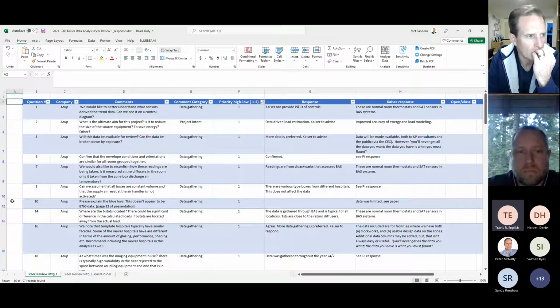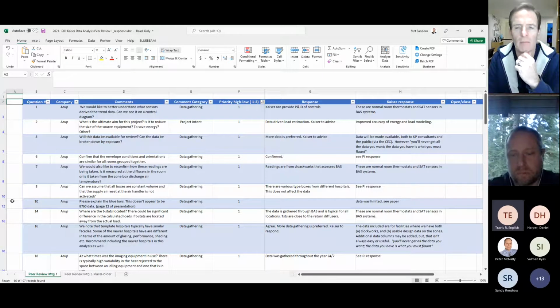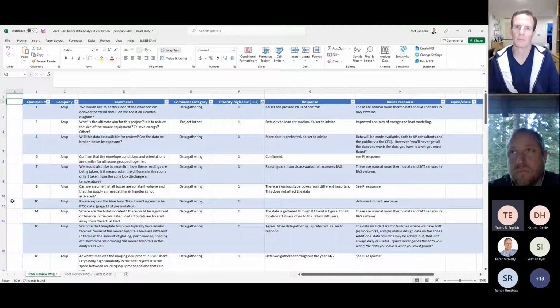All of you on the phone doing Kaiser work as design engineers know it's tough right now, because we are also asking our design engineers to articulate the design of the systems in the neutral condition. If you've been on the phone with us in the last couple of months, we say your BOD not only needs to include the peak load design, but also very clearly describe what are all the CFMs, what are all the GPMs, what are all the valve positions at 9 a.m. in the morning when it's 69 degrees outside.